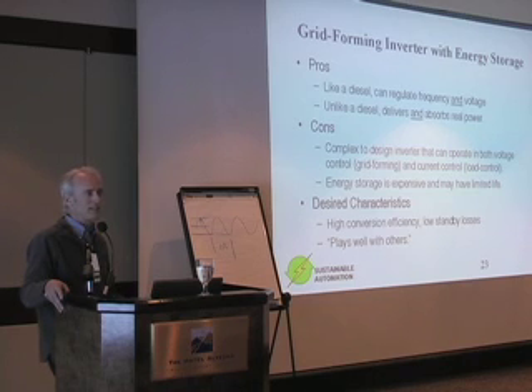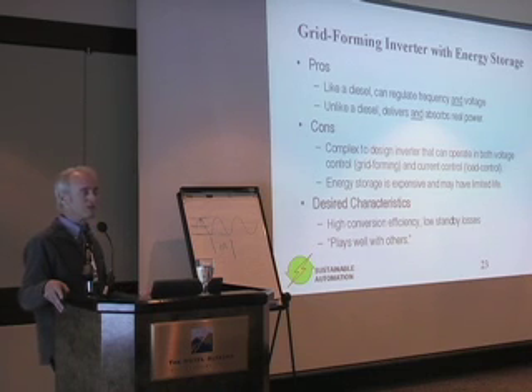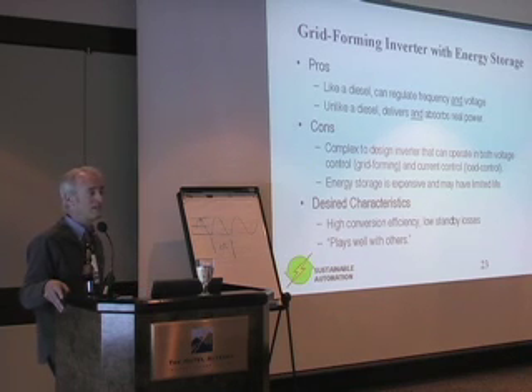Inverters are a newer technology. There are voltage source inverters, there are current source inverters. There are relatively few that do both, and the challenge is the design becomes relatively complex when you're trying to provide a system that can operate in both modes. Either it's the master on the grid or it's assisting the diesels in a power control mode. And performing those transitions gracefully is still something that many people are working on. We're spending a lot of development effort working out the kinks in that. So there's some complexity associated with power converters that you don't find in some of these other components.